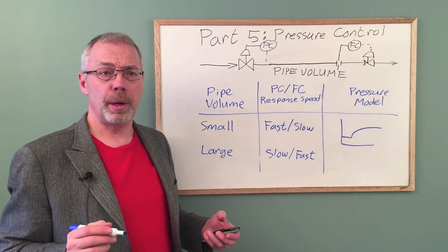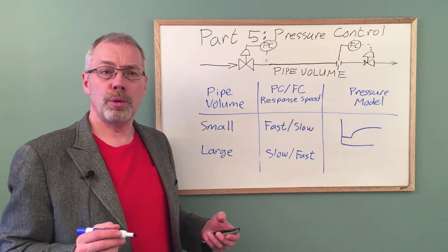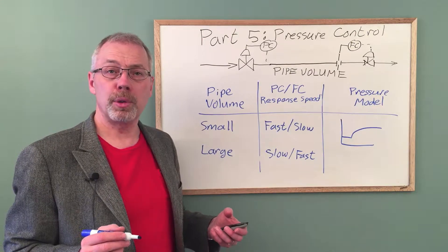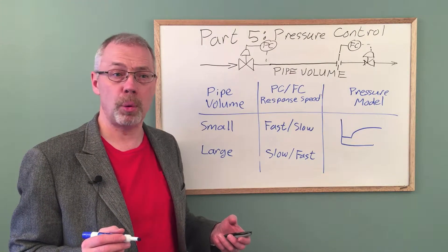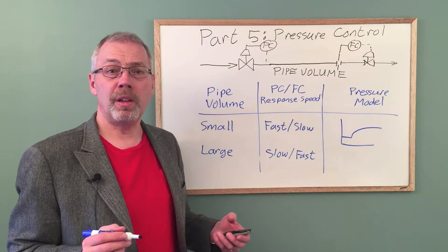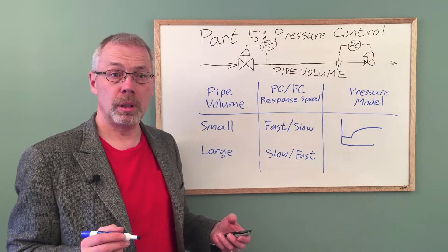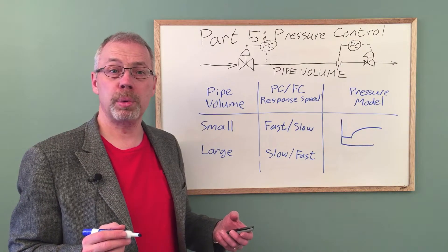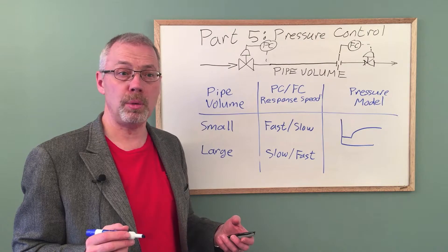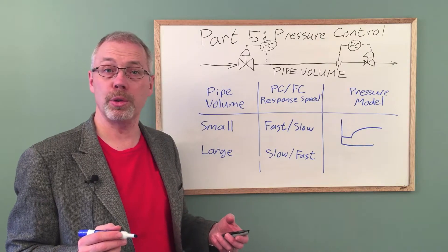How will the pressure respond? Since the flow controller is faster, from the perspective of the pressure control, the flow always appears to be on set point. The pressure valve opens up and admits more fuel gas. The outlet flow rate is constant. The pressure in the supply header increases continuously as more gas enters the piping.